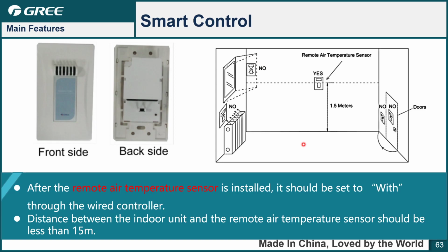Next one is the remote air temperature sensor. If the customer wants to connect a temperature sensor in the room for detection, they can choose this one. You can place this remote air temperature sensor in the room, and then the unit will get the feedback from this sensor and use this value as the control temperature point. For this sensor, the standard length is 15 meters. Yeah, 15 meters.